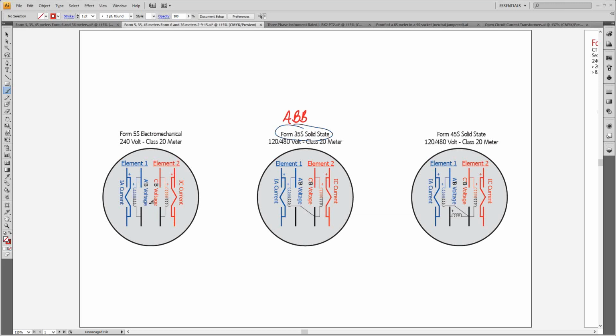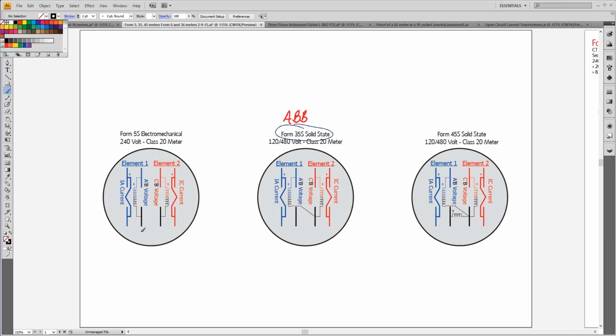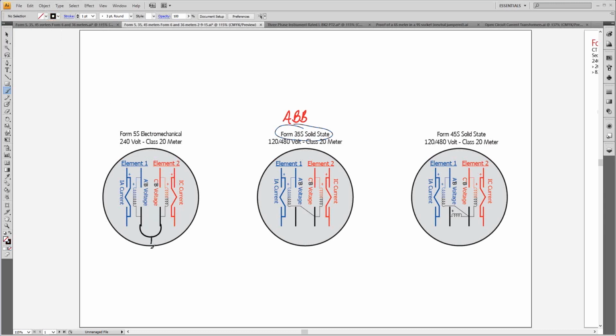And so if you're on a three-phase 3-wire delta, you would put a jumper in between these two, and you'd put B phase here. That would fit with Blondel's, because you're measuring current in A phase and current in C phase. B phase is the unmetered leg, but Blondel says in order to meter this correctly, you have to have a tie to the B phase conductor with both potential coils, or a common tie to both potential coils. So that meter comes out.